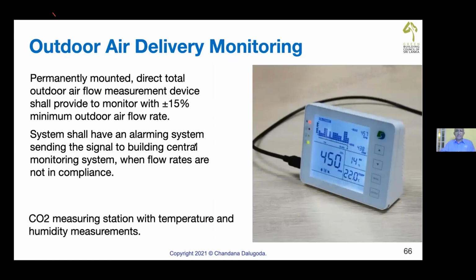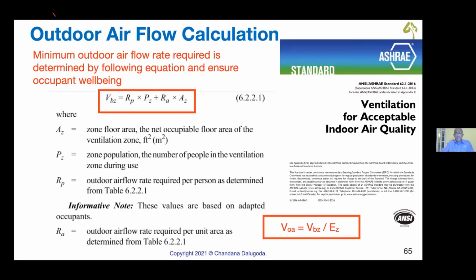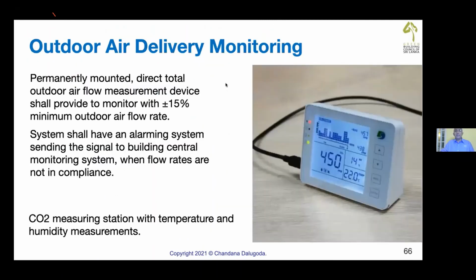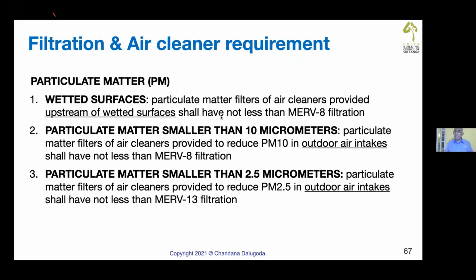I'm discussing that. To comply with this rating system, Green Building Council Sri Lanka, you need to comply with another thing, outdoor air delivery monitoring. What is the CO2 level? CO2 meters have to be used. And for the filters, you'll have to use certain high grade filters like MERV 13 and MERV 8. Now, air handling units must have MERV 13 filters. And outdoor air intakes, yes, for PM 2.5 micron filtration. For PM 10 filtration, larger particles, you need MERV 8. So, if you use MERV 13, it is fairly okay for COVID mitigation. Another advantage.